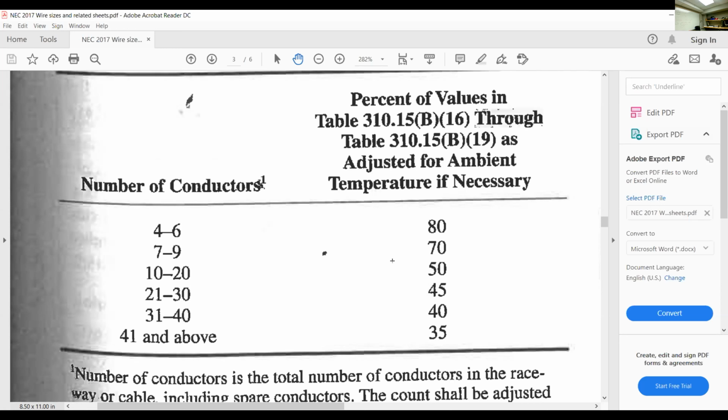How many of you that have jobs already have seen melted wires in conduit? I see 2 hands, 3 hands, 4 hands. There's 4 hands out here of people that say they've seen melted wire, including me. That's 5 of us who've seen melted wire, like melted wax in conduit. I pulled them out before because of issues like what we're talking about that were not planned properly. Things weren't planned properly. It's very embarrassing, very costly, damaging equipment and downtime and stuff.